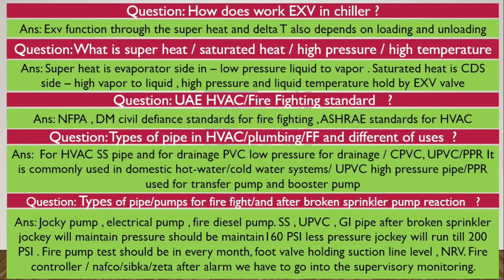Question. Type of pipe and pump for firefighting, and pump reaction after a broken sprinkler. Type of pump: jockey pump, electrical pump, fire diesel pump. Type of pipe: SS, UPVC, GI pipe. After a broken sprinkler, the jockey will maintain. If you have a single broken sprinkler, that jockey is enough to maintain. Also the jockey maintains up to 160 psi to 200 psi.